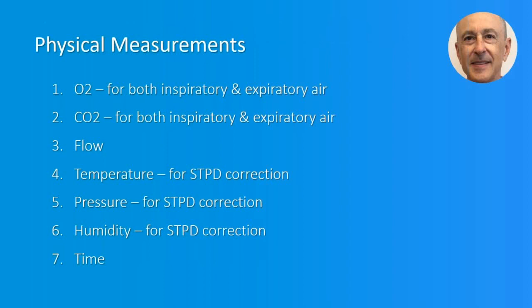Metabolic carts make quite a few physical measurements: oxygen concentration for both inspiratory and expiratory air; carbon dioxide concentration for both inspiratory and expiratory air; flow, where flow and time are used to derive breath volume and determine the start and end of a breath; temperature, pressure, and humidity used for STPD correction — noting that some metabolic carts require the operator to provide those devices; and time measurements used to derive breath volume and synchronize the breath with flow.